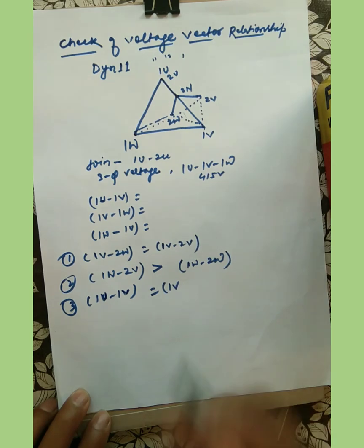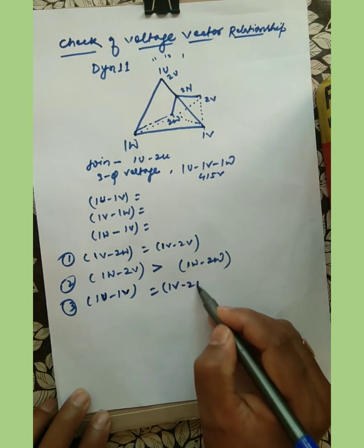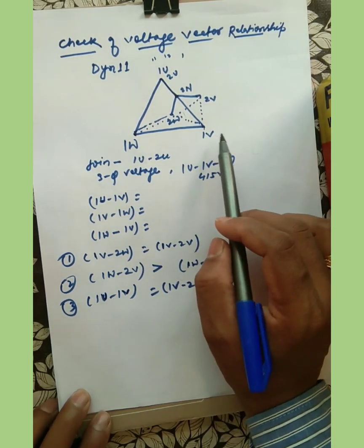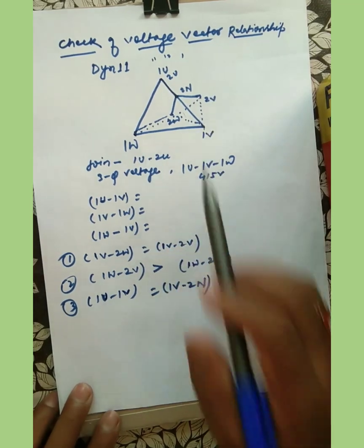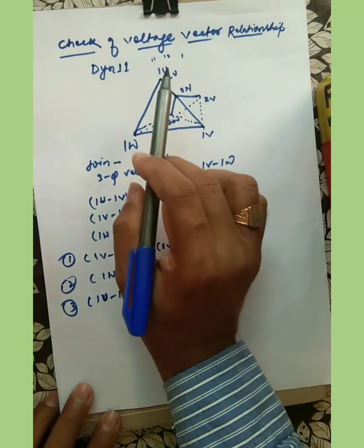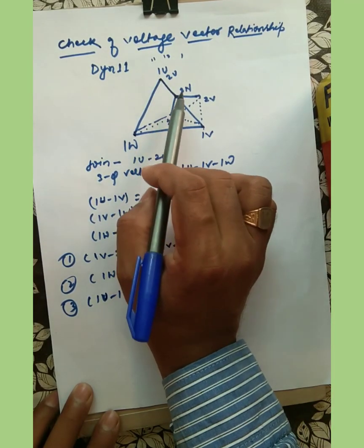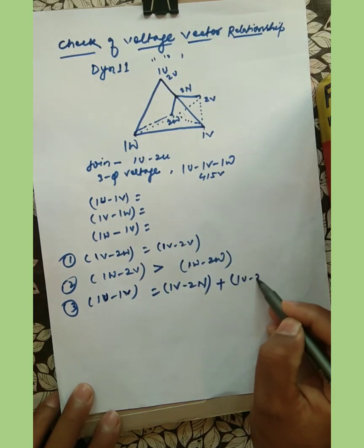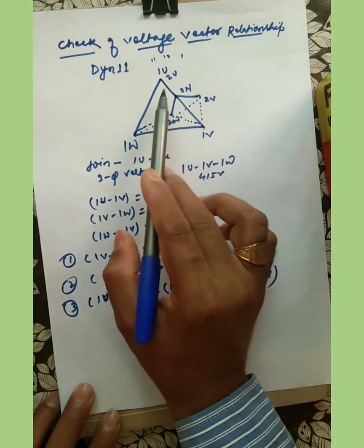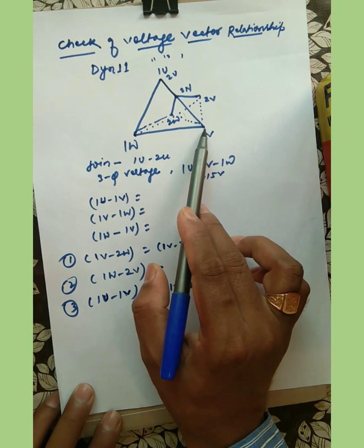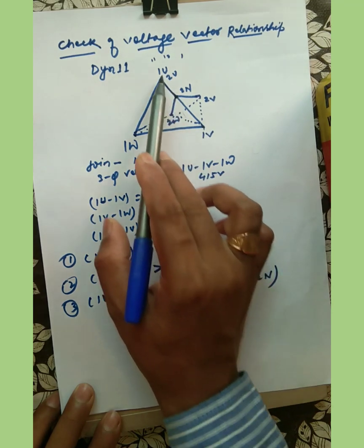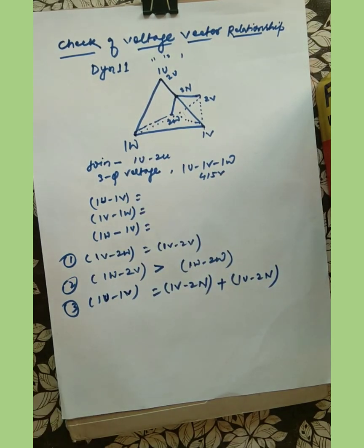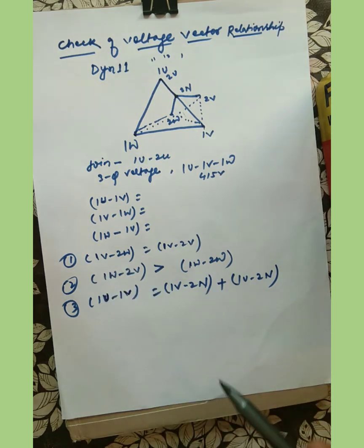The third relationship is that the voltage between 1W and 2N plus the voltage between 1V and 2N should equal the primary line voltage 1U-1V. If we verify these three equations, then we can prove that our vector group is DYN11. Now I am going to show the test result.